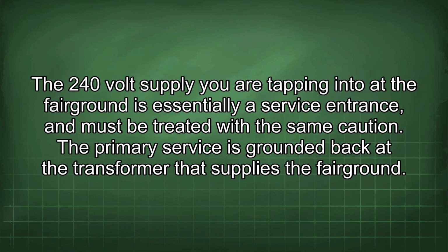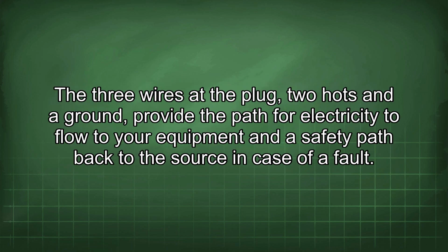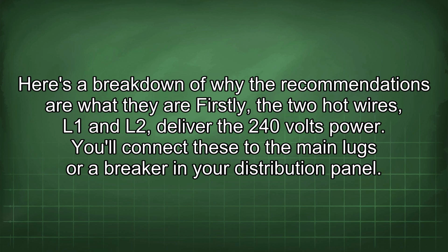The 240-volt supply you are tapping into at the Fairground is essentially a service entrance and must be treated with the same caution. The primary service is grounded back at the transformer that supplies the Fairground. The 3 wires at the plug, 2 hots and a ground, provide the path for electricity to flow to your equipment and a safety path back to the source in case of a fault. Here's a breakdown of why the recommendations are what they are.